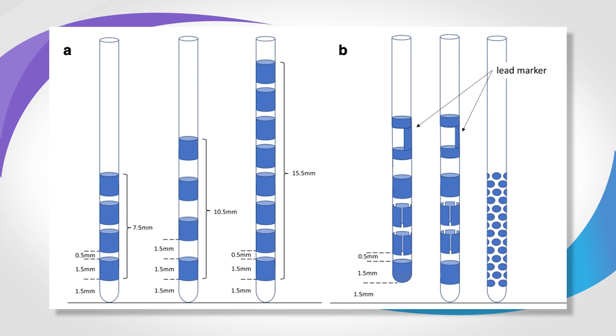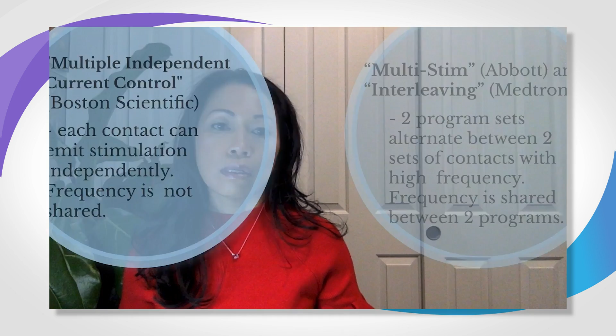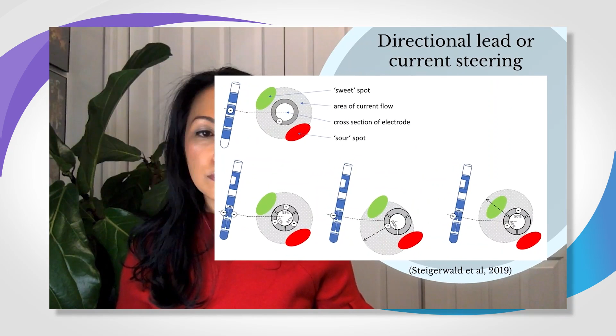What we're doing with stimulation is just changing the shape of the field of energy. As I mentioned earlier, co-activation is when we have 2 different segments activated and power is shared between those 2 contacts. We can see that in multi-stim on the Abbott device or interleaving on the Medtronic device. We can set 2 separate programs and they share a frequency between those 2 programs. Or in the Boston Scientific device, we can send stimulation from individual contacts independently, and the frequency is not shared. Those are all terms for co-activation.